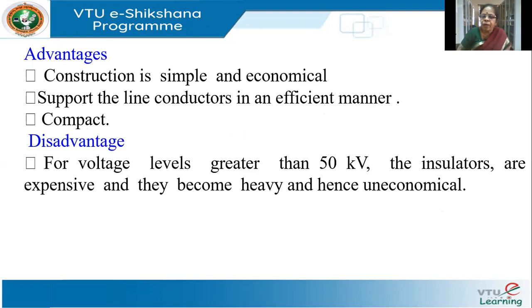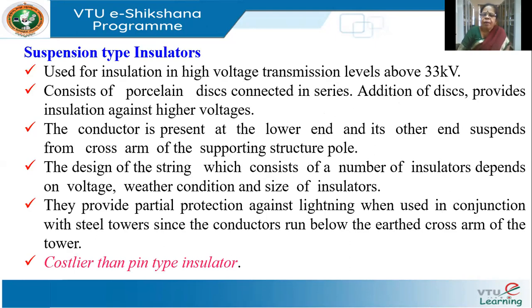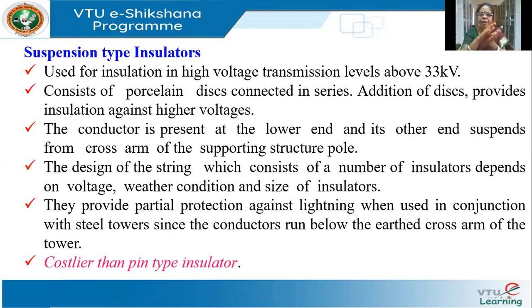The disadvantage is that it becomes very expensive for higher voltages. Next, we have suspension type insulators, which are used for voltage levels above 33 kV. In suspension type insulators, you have discs — this is also very common and you will have seen it very often. If I want more insulation, I simply add more discs. It is modular.